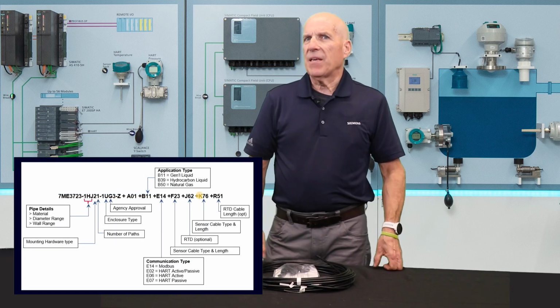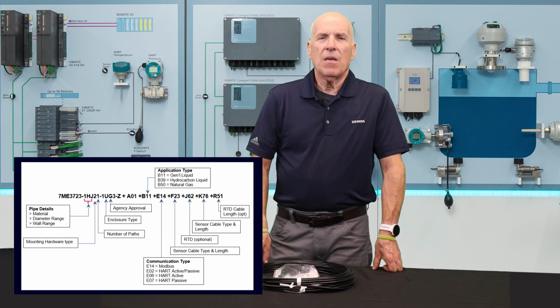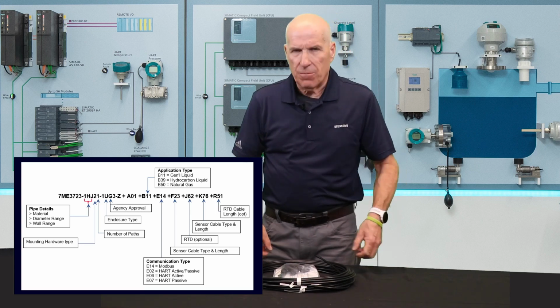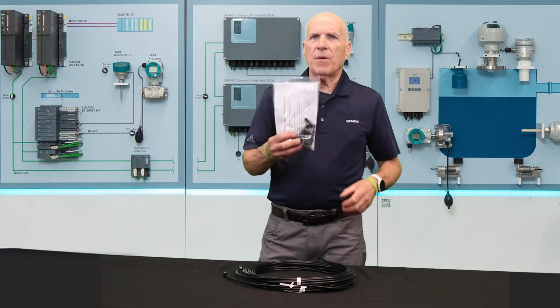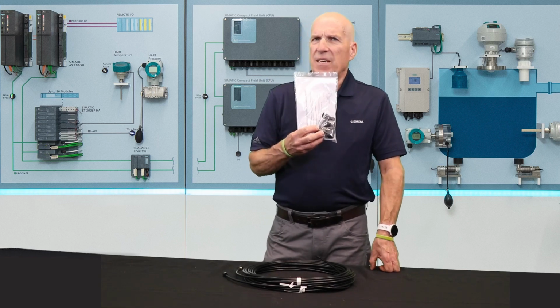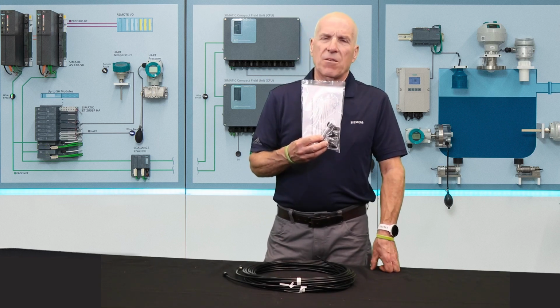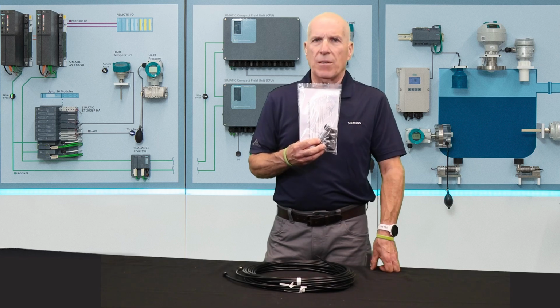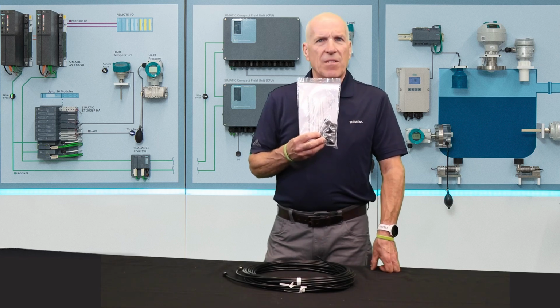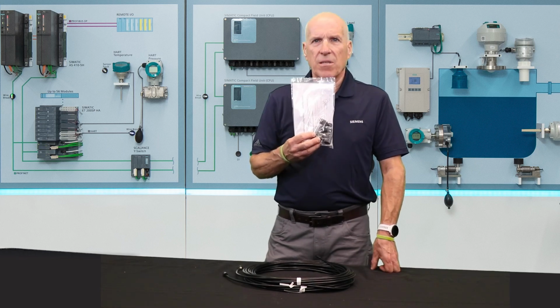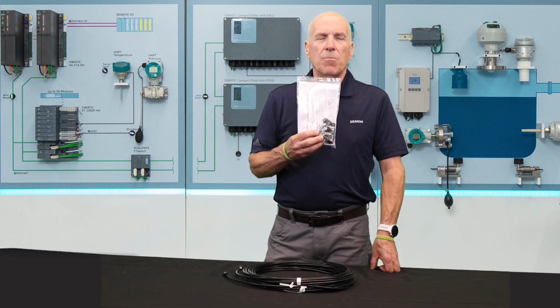Cable is identified by the K adder for single path systems or the J adder for dual path systems in the system part number. Along with the cables, a termination kit is supplied. The sensor end of the cable is unterminated to facilitate pulling them through conduit. The termination kit contains the necessary F connectors, shrink sleeving, labels, and glands to complete the cable installation.